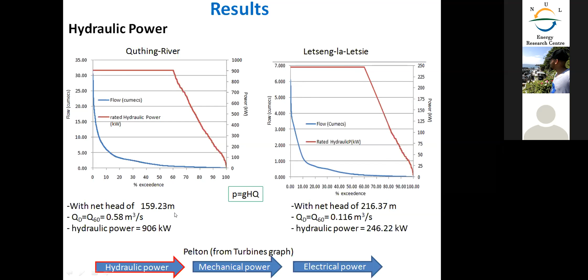Now the next step will be to determine the mechanical power. Looking at our net head and flow rates, it can be seen that the heads are high and the flow rates are very low. So from the turbine graph, the turbine that can feature well there is a Pelton turbine. Using the Pelton turbine, with a typical efficiency of 90% from literature, applying this to the hydraulic power, the output of the Pelton turbine will be 815 kilowatts for typical performance.